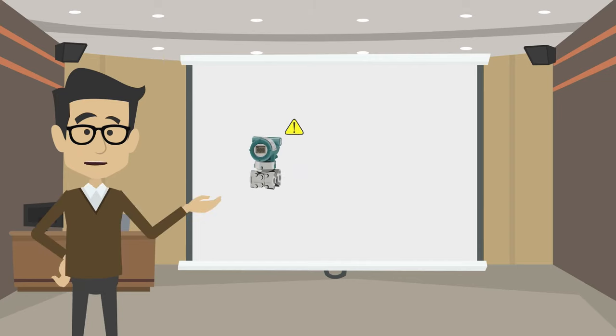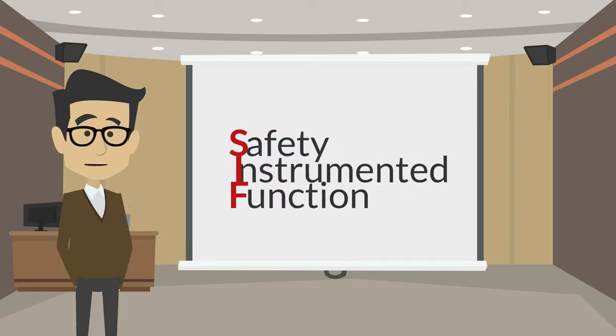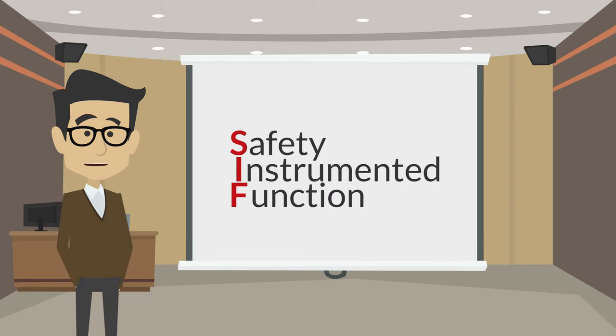If the SIS senses a hazardous condition, it will send a signal to a final element, typically an actuated emergency shutdown valve, or ESDV, to isolate or shut down the system.